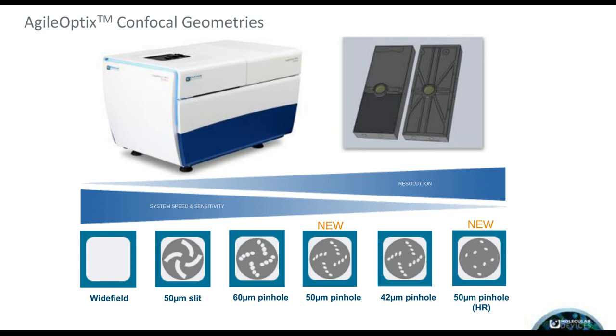Beyond this, the instrument can bring different types of what are called disk geometries — different sizes, different shapes, different spacing of pinhole types. This brings great flexibility in how you adapt the performance of the instrument to the type of assay you run. Not every day do you need high-resolution confocal; sometimes you just want wide field. This is available through a simple drop-down menu in the software. We have two new geometries recently released, mostly directed towards 3D imaging and tissue imaging.